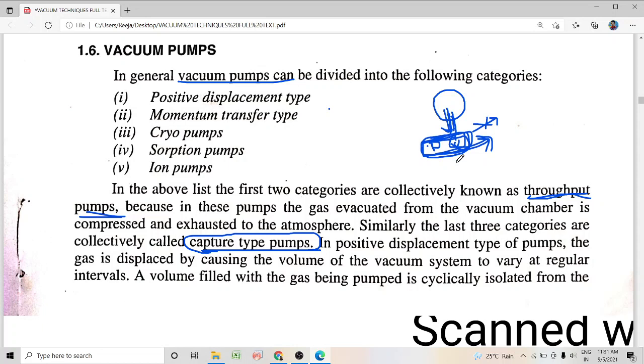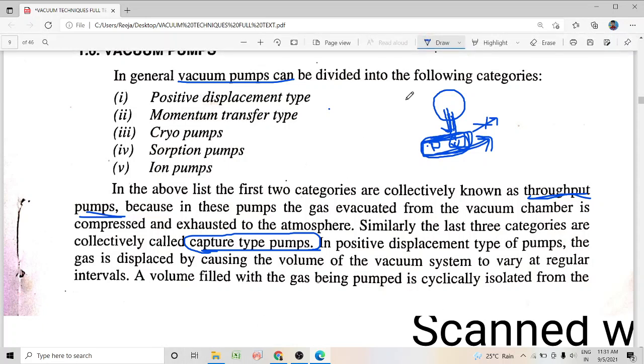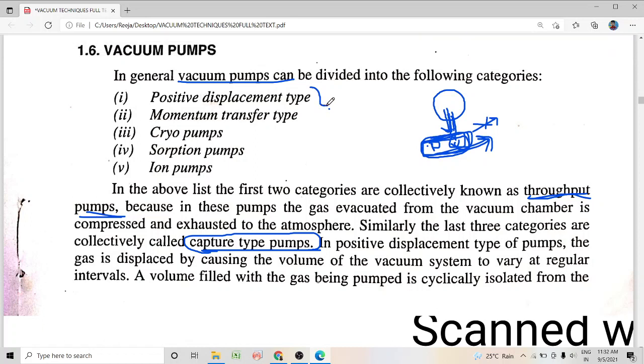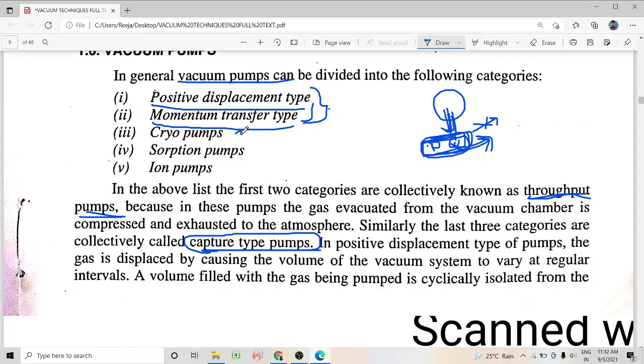So vacuum pumps are divided into two: throughput type pumps, where the gas molecules extracted from the vacuum vessel are compressed and exhausted to the outside, and capture type pumps, where the gas molecules extracted from the vacuum chamber are not exhausted to the outside but instead trapped on the walls of the vacuum pump. Throughput type pumps include positive displacement type pumps and momentum transfer type pumps, whereas cryopumps, sorption pumps, and ion pumps all come under capture type pumps.